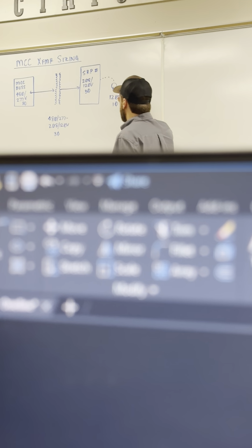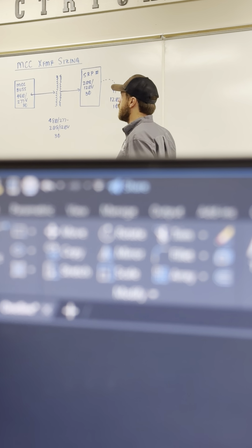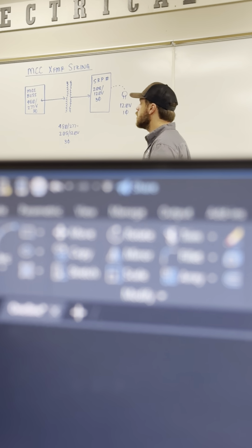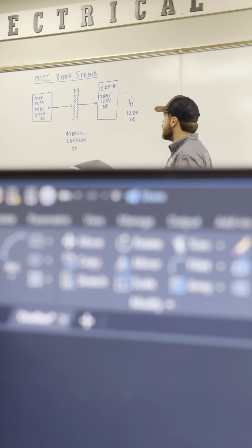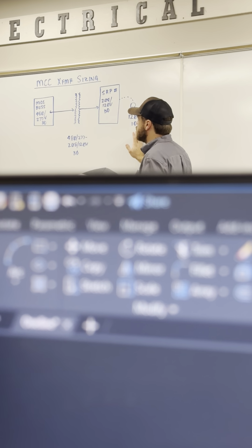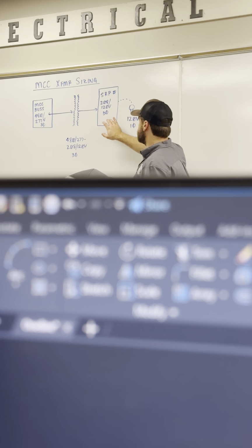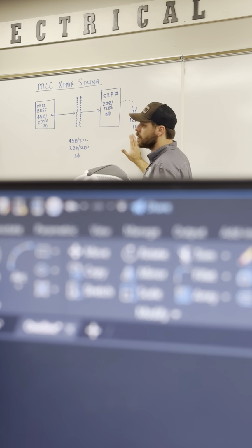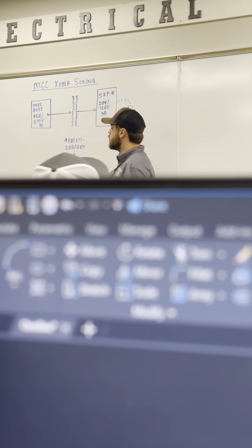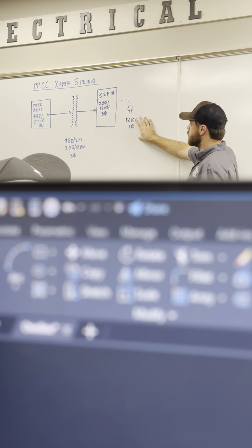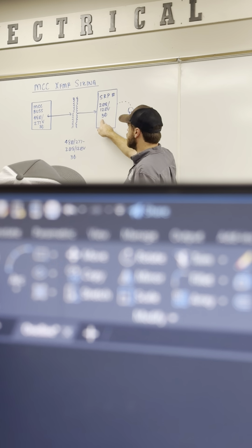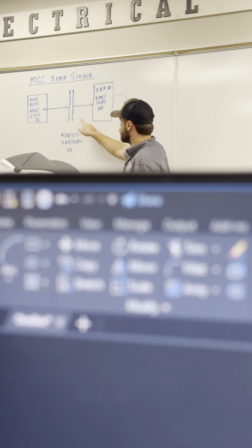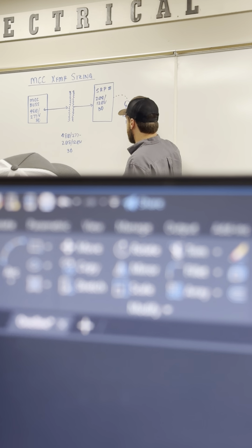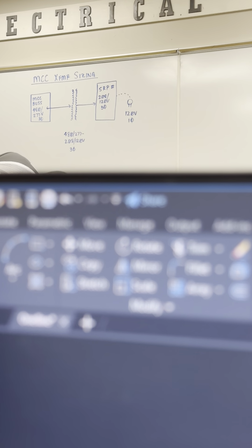So we could say, all right, well, each MCC has X amount of receptacle circuits being fed out of it. So we could size the transformer specifically to that load. You could do it that way. However, let's just say you only had a handful of receptacle circuits being fed out of this MCC, so you size your transformer according to that. Well, there's only one panel that we're installing. So if you ever come back in and put more receptacle circuits, you would potentially have to change out this transformer. So rather than basing it off of the number of receptacle circuits that you actually have, we're going to look at what is the maximum capacity that this panel can handle. And we're going to size our transformer to handle this capacity, not our actual number. Does that make sense?